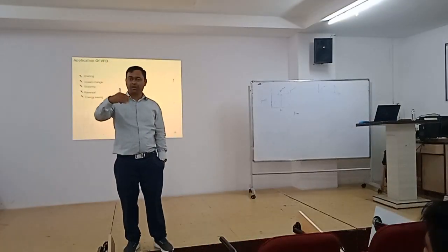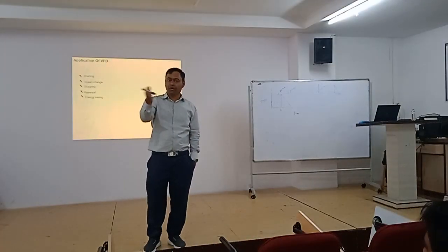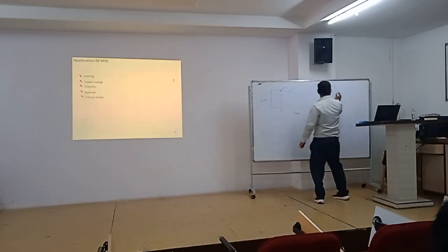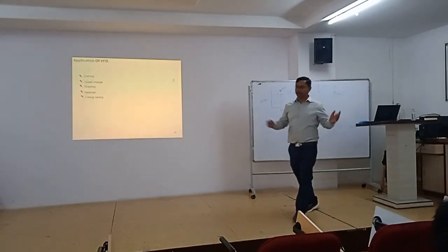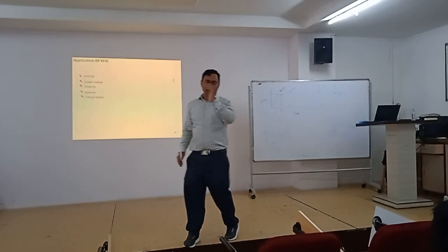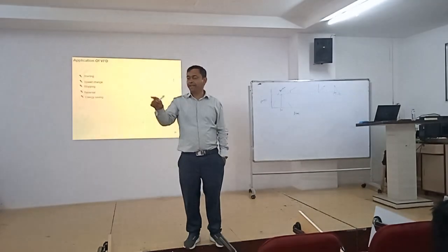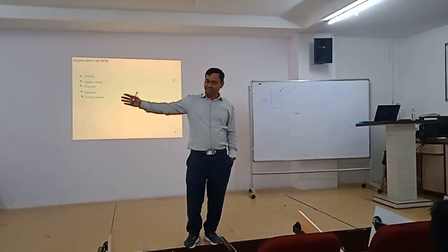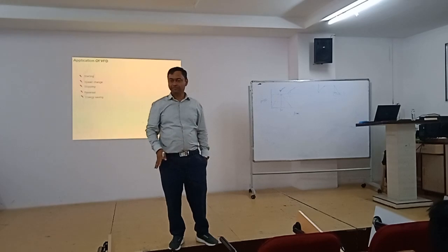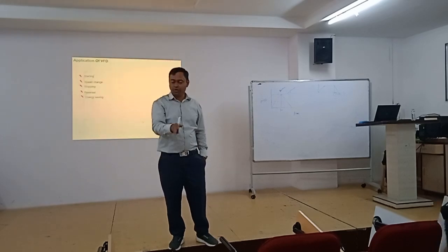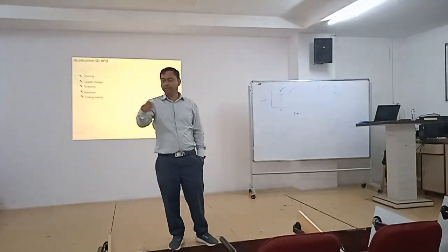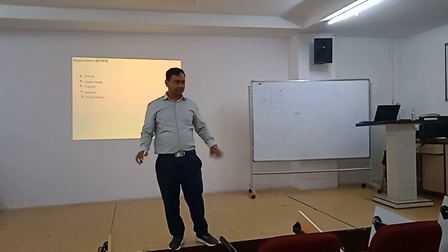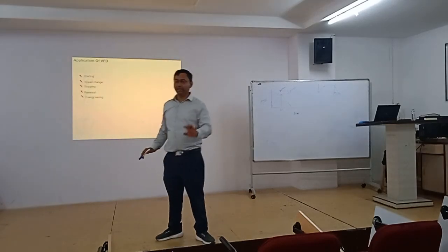Just out of curiosity, just for fun, in the practical we did, we ran our motor and changed that 10 seconds to 0.1 second. The motor was not connected with the load, and when you press stop, the motor stops as soon as you press it. It will overcome the inertia to stop rotating. I hope this is clear.